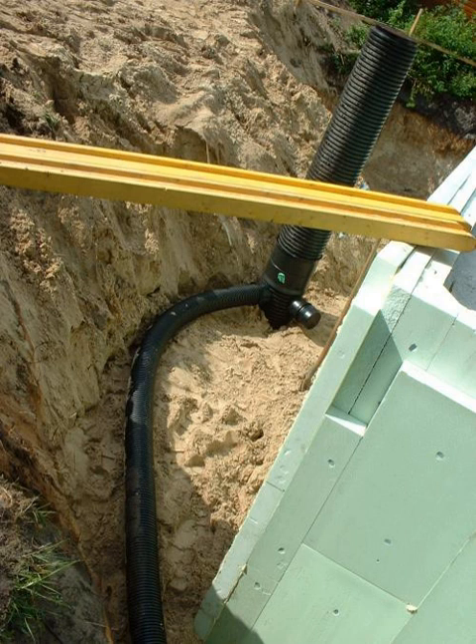Joints connecting the tubes together must be tight enough to prevent water or gas infiltration. In certain geographic areas, it is important that the joints prevent radon gas infiltration. Porous materials like uncoated concrete tubes cannot be used. Ideally, earth tubes with antimicrobial inner layers should be used in installations to inhibit the potential growth of molds and bacteria within the tubes.